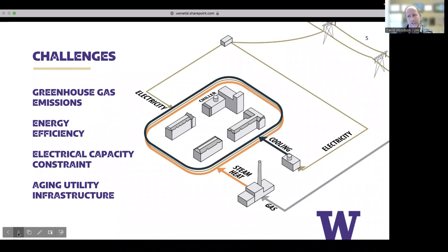I'd also add that the fuel switch is from natural gas that we burn to create steam, to using electricity to run heat pumps. I'll explain two other ways. I described the cooling tower where I'm lifting that low-grade heat we dissipate to the atmosphere from the heat pumps or cooling towers. Instead of putting that heat into the air, we put it into the hot water system, displacing natural gas. That's why that's a fuel switch.